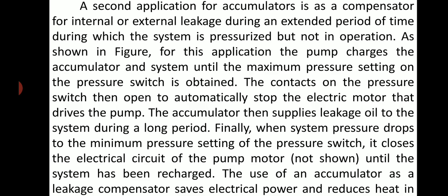A second application for accumulators is as a compensator for internal or external leakage during an extended period of time during which the system is pressurized but not in operation. As shown in the figure for this application, the pump charges the accumulator and system until the maximum pressure setting on the pressure switch is obtained. The contacts on the pressure switch then open to automatically stop the electric motor that drives the pump.